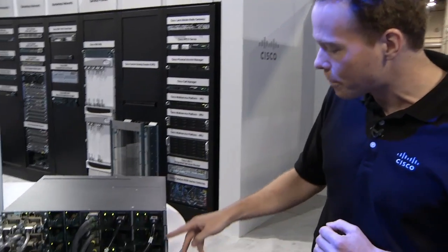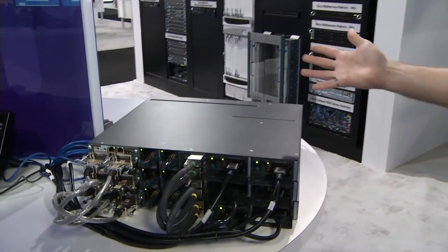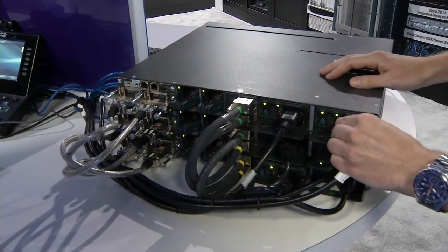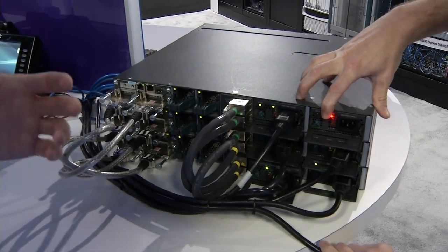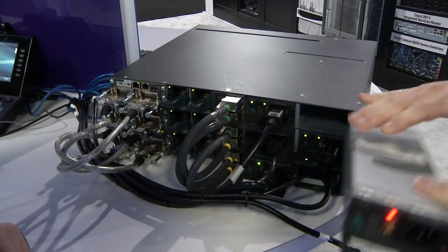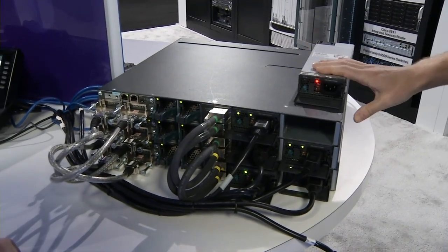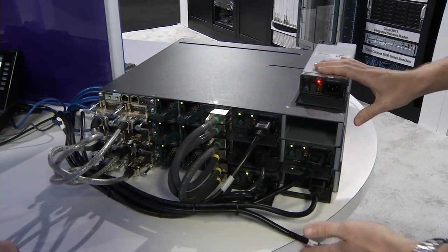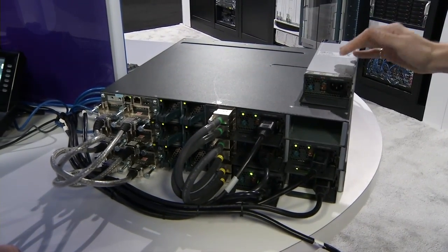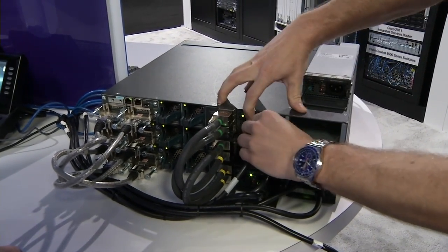So an example of what it does. Here you have two power supplies in each of those switches, so you would think everything is redundant, of course. So I can create a failure on the first switch. So now you're actually unplugging power from the switch. And then just to prove to everybody there's no power: failure of one power supply or failure of the power source, second power supply, no big deal, everything is like you expect.